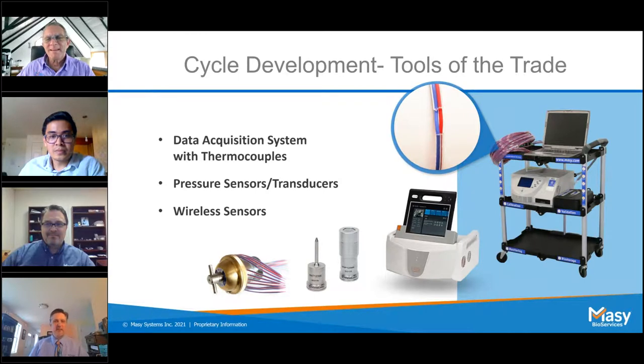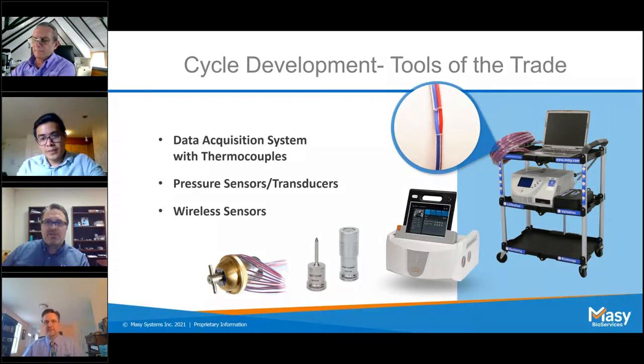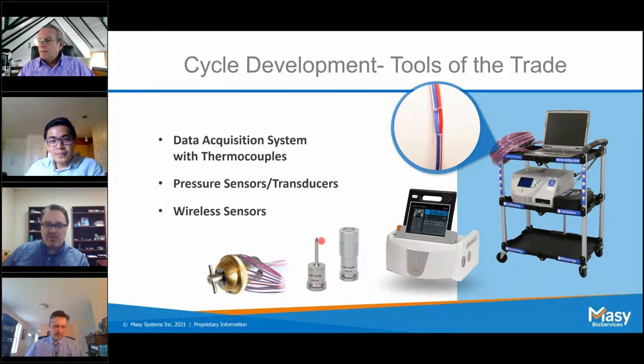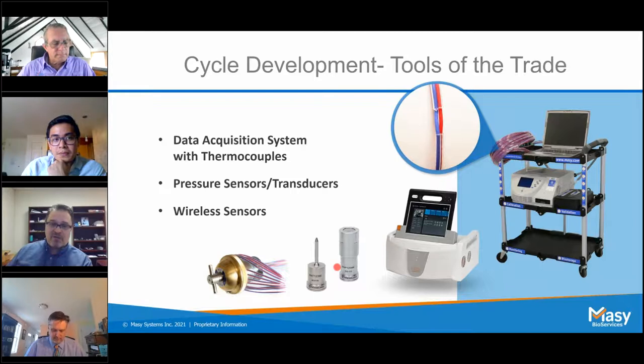Last but not least on this slide, Sylvan, can you talk about wireless sensors? Certainly. So the ones there that you see, those small stainless steel devices to the right of the feed through, those are data trace loggers. You can use wireless systems in a sterilizer, but there are pros and cons, right? They may be more convenient than having to run wires through a feed through and doing the additional leak tests, but they are battery powered devices. You need to make sure, especially be very sure, that the gaskets are intact and that they're properly closed up. You don't want steam getting inside one of those things. It will destroy them. So there's definitely some preparation and care involved, but those are the two items shown there. One is a temperature sensor and the one to the right is a pressure sensor.